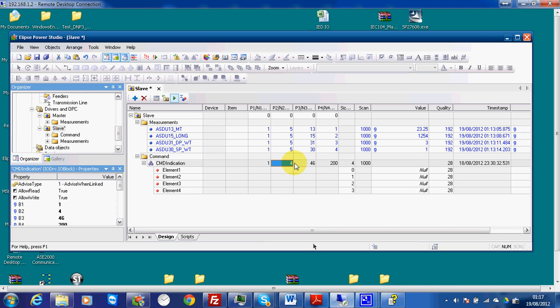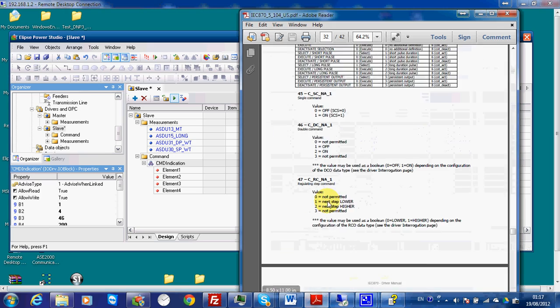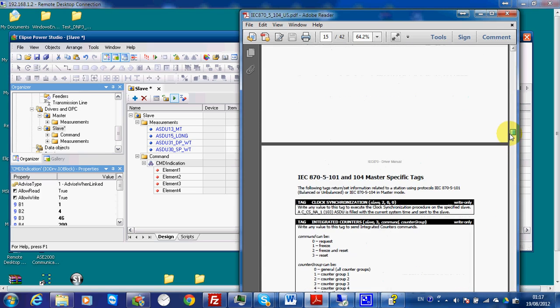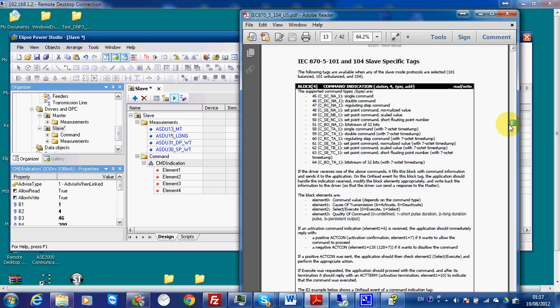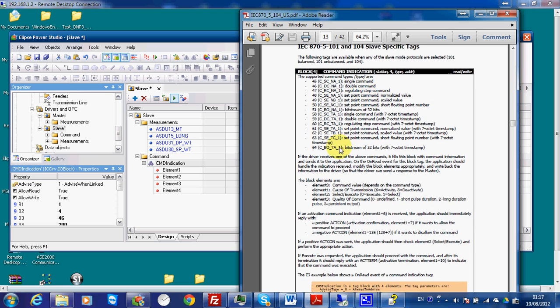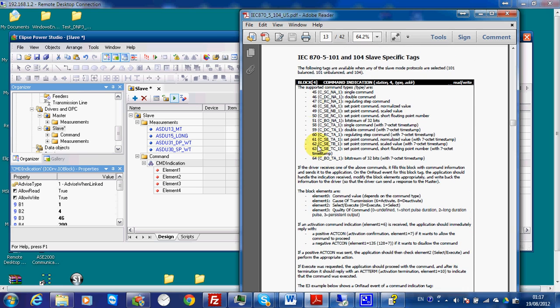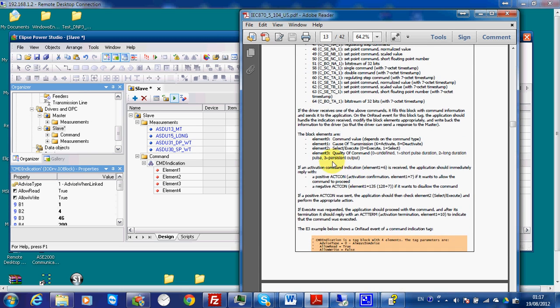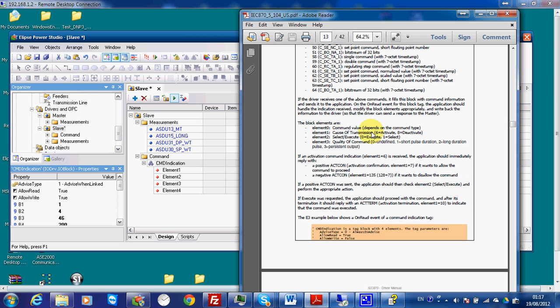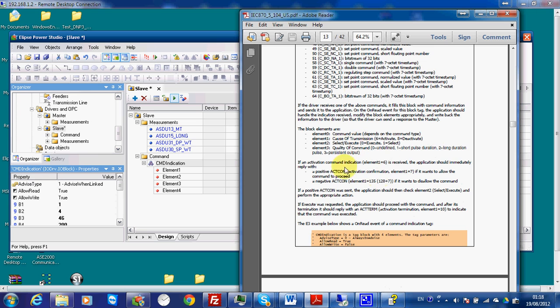This function is for the CMD indication. The CMD indication is a block that receives information from a command. In the indication block, you have different supported ASDUs. I choose ASDU type 46, which is double command. The elements available are: element 0 is the command value (for double command: 0, 1, 2, or 3); element 1 is cause of transmission (6=activate, 8=deactivate); and element 2 is select or execute.